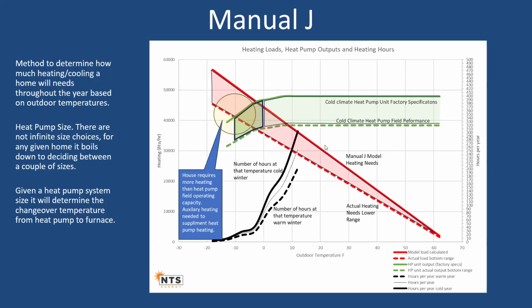And I should have actually put that in. I'll have to add that in. So you want to do this in here. Now realize what's going on is this little bit here is your supplemental. And so my heat pump might go to -13. Like I said, I just looked up with the new refrigerant, -15, -20. So it's tailing off. My supplemental gas, I don't worry about it. I just set the furnace, it does this much heat. Electrical, I want it to make up this difference. I don't want to overdo it.